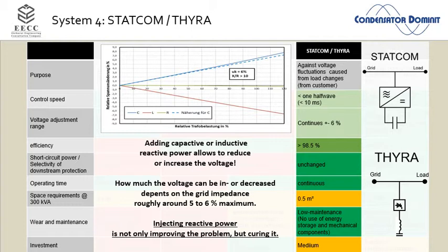Now, one of our customers nearby runs a factory, an automotive supplier. Every item that leaves the factory has to undergo exactly a 24-hour burn-in test. Every morning, exactly 3 minutes past 7, or the next day 5 minutes past 7, when the thermals start and the air begins moving, the bird starts flying and causes a voltage sag. So you're running a 24-hour burn-in test, and after 23 hours and 56 minutes, the bird craps on your overhead line.